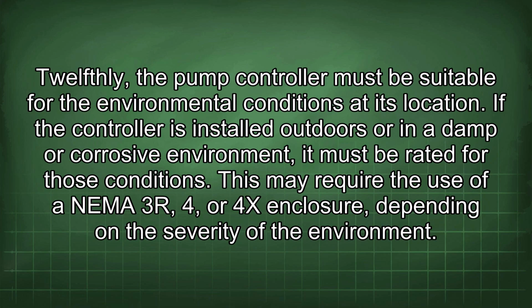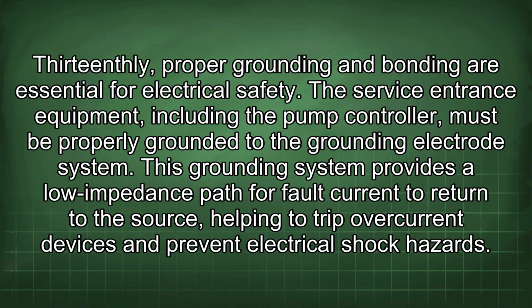12thly, the pump controller must be suitable for the environmental conditions at its location. If the controller is installed outdoors or in a damp or corrosive environment, it must be rated for those conditions. This may require the use of an NEMA 3R, 4, or 4X enclosure, depending on the severity of the environment. 13thly, proper grounding and bonding are essential for electrical safety.